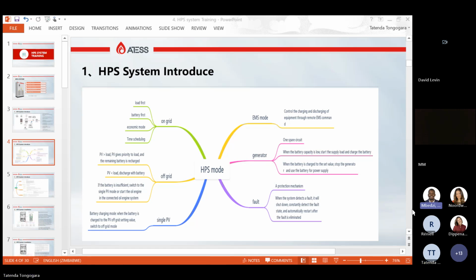So the maximum number of HPS that you can parallel and still continue to have seamless changeover is 4. I've seen a site where they had 5 HPSs, and I saw in your recommendation that it's 4. I'm not sure if that's something that will be updated, or for recommendation it's still just keeping to 4 HPSs in parallel. At the moment, keep it to 4 HPS in parallel. The same applies to the PCS. I'll do a presentation on the PCS after this. So just keep it to 4.